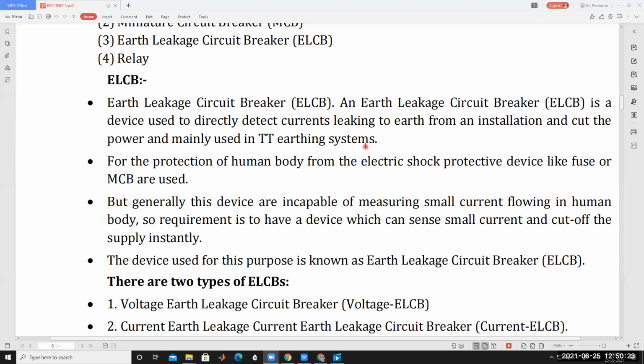By using an ELCB, we can protect human beings. The earth leakage current flows into the earth leakage circuit breaker, and it trips the contacts from the supply. It opens the contact and isolates the faulty device from the supply. In this way it protects whenever there is an insulation failure or winding failure inside the device, causing a short circuit with the ground. If you touch the device, the fault current passes through the human body, which is very harmful.